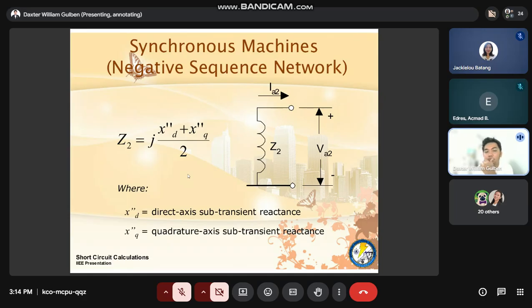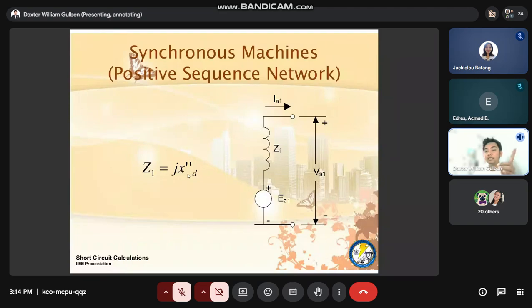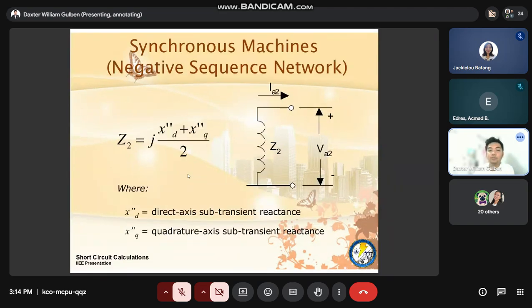Similarly with your negative sequence network, your Z2 has components of direct axis subtransient reactance and quadrature axis subtransient reactance. But in most cases, there is no XQ. So that is why in most cases, Z1 is basically equivalent to Z2. So you can just average the direct axis and quadrature axis equivalents from the nameplate rating of your machine, then divide it by 2.